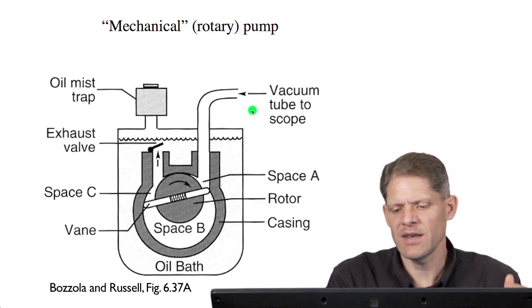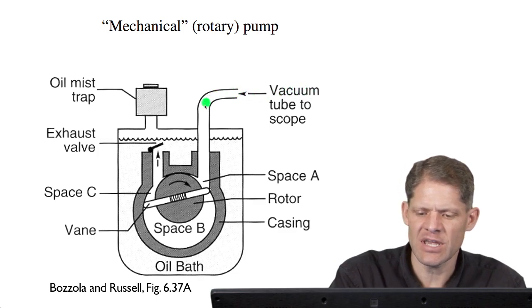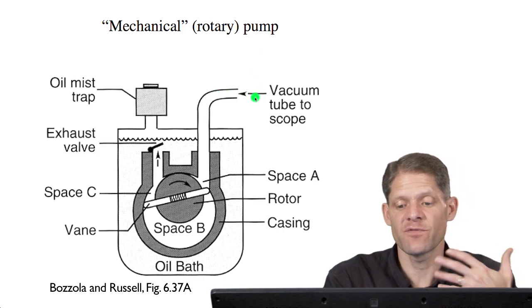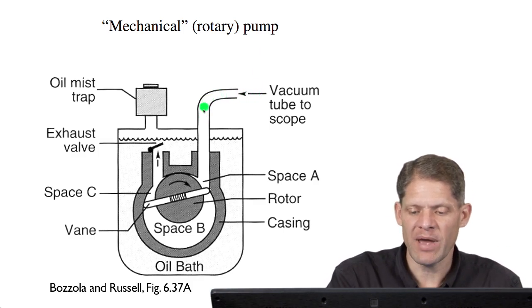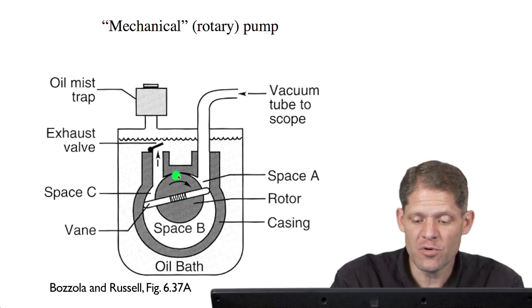The anatomy of this pump is that the microscope column would be attached, for instance, to this input tube. And so gases from the microscope column as it's first being evacuated would pass through here.